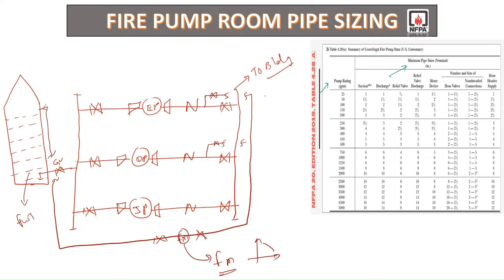Apart from this, we have one more line going to the controllers. A sensing line from the diesel discharge goes to the diesel controller, from the electric discharge line a sensing line goes to the electric pump controller, and from the jockey side it goes to the jockey controller.